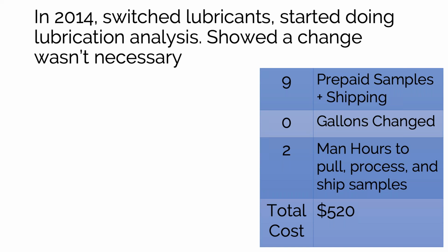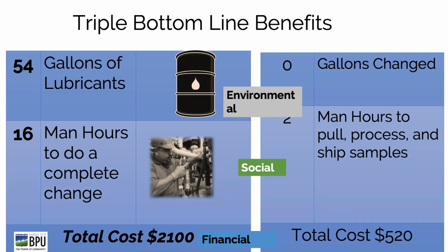So every year they would take 9 samples. They would take 2 hours to pull those samples, and the total cost with shipping and analysis was $520. So every year they go and do this, and they have found that they can go 4 years without changing the lubricant.